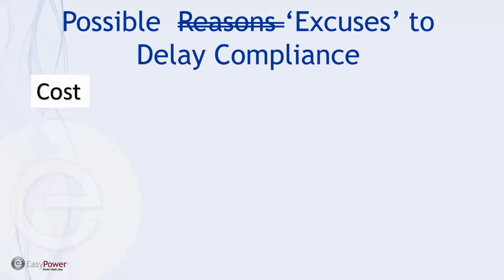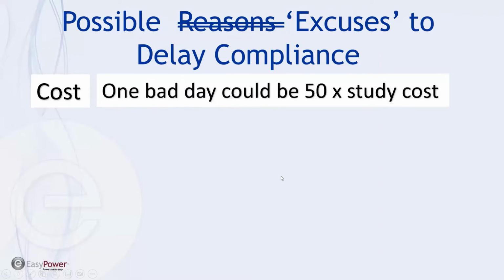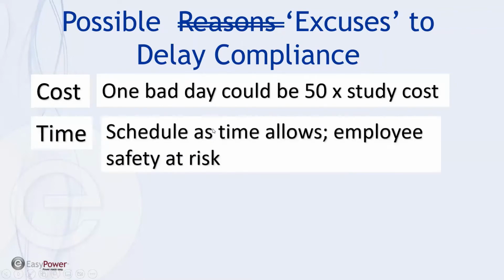Well, I compiled a list of possible excuses, if you will. One is cost. It does cost some amount of money to do an arc flash study, but one bad day that involved an arcing fault could end up being 50 times the cost of the original study itself. It does require some amount of time, but you can schedule as time allows, and it is something that you weigh against the safety risk of employees.